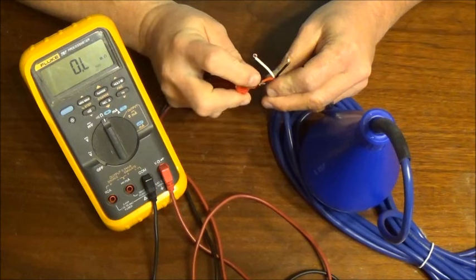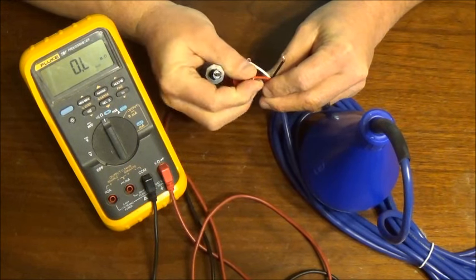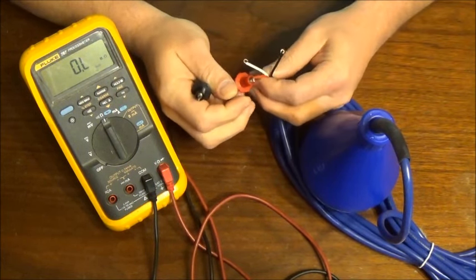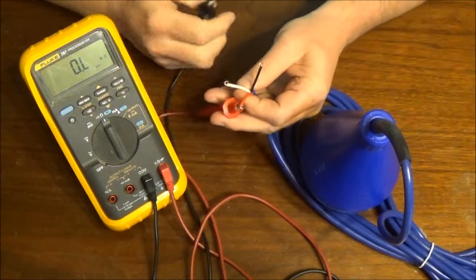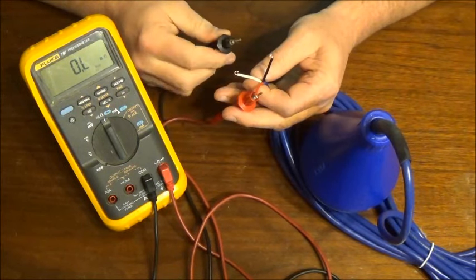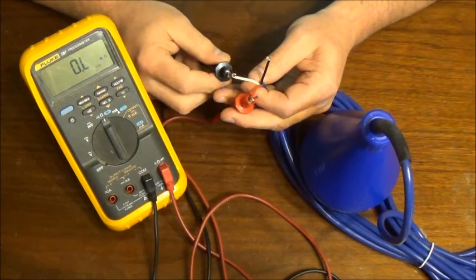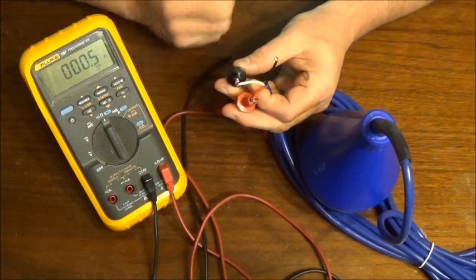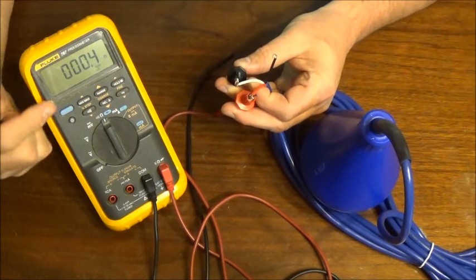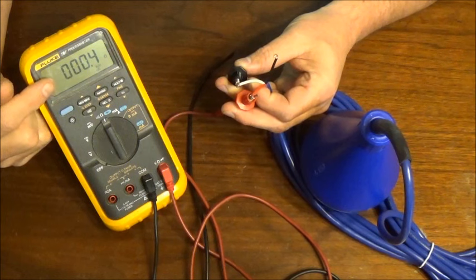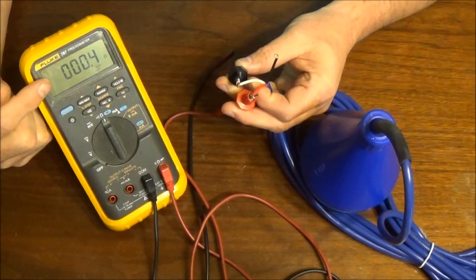Putting a lead there, knowing that this red conductor is the common of the two conductor contacts, and then going to the white, you will notice that now we are reading the short condition: near zero, 0.3 or 0.4 ohms of resistance.